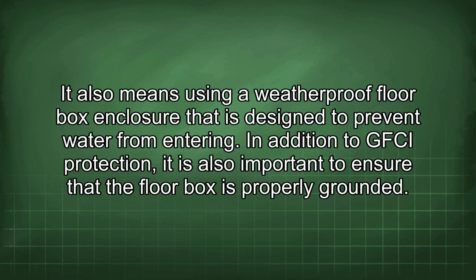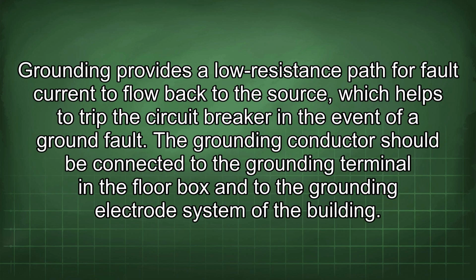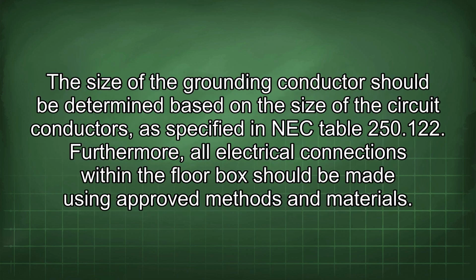In addition to GFCI protection, it is also important to ensure that the floor box is properly grounded. Grounding provides a low resistance path for fault current to flow back to the source, which helps to trip the circuit breaker in the event of a ground fault. The grounding conductor should be connected to the grounding terminal in the floor box and to the grounding electrode system of the building. The size of the grounding conductor should be determined based on the size of the circuit conductors, as specified in NEC Table 250.122.